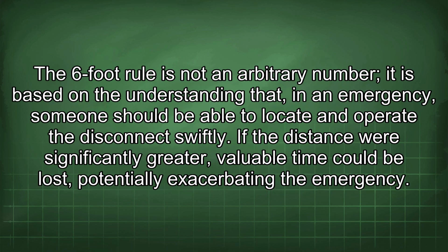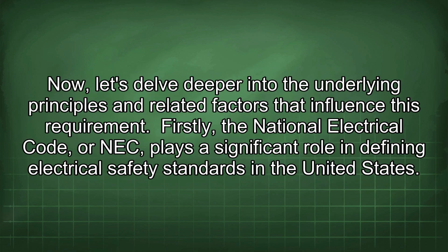The 6-foot rule is not an arbitrary number. It is based on the understanding that, in an emergency, someone should be able to locate and operate the disconnect swiftly. If the distance were significantly greater, valuable time could be lost, potentially exacerbating the emergency. Now let's delve deeper into the underlying principles and related factors that influence this requirement.